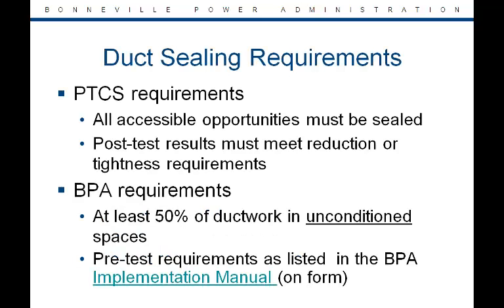All duct sealing jobs must meet both the duct sealing requirements outlined in the PTCS specifications, as adopted and posted to the ResHVAC website, and BPA requirements outlined in the implementation manual. PTCS requires that all accessible opportunities be sealed. The duct leakage post-test must also meet the reduction or tightness requirements as outlined in the specification.